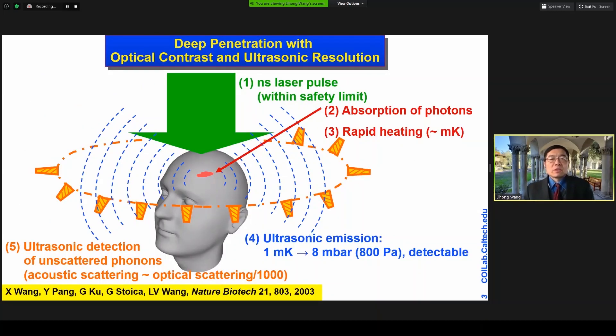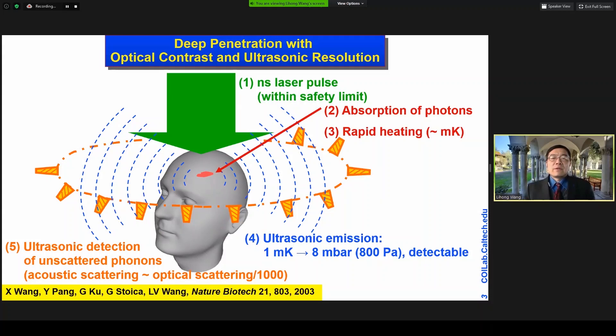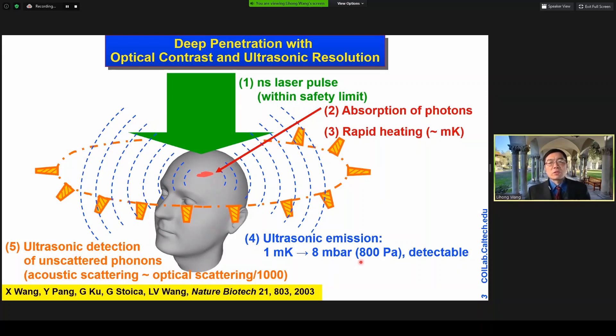In photoacoustic tomography, we typically use a nanosecond laser pulse. We broaden the laser beam such that the energy per area is within the safety limit. When photons diffuse deeply into biological tissue, photons are absorbed, and light absorption generates rapid heating. Every milli-degree gives us 800 Pa of pressure, which is detectable already. Within the safety limit, we can heat up to hundreds of milli-degrees, so we have a sufficient signal-to-noise ratio to work with.